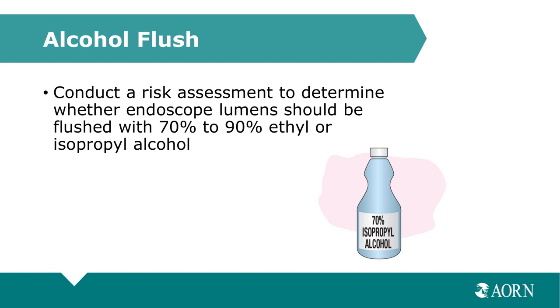Many clinical practice guidelines and many experts in the field recommend manual or mechanical flushing of the endoscope lumens with alcohol because it helps to facilitate drying of the endoscope lumens by binding with residual water, and this enhances evaporation. However, flushing of the endoscope lumens with alcohol just might not be necessary if your endoscope has been effectively cleaned and thoroughly dried. And because of the fixative properties of alcohol, this practice is not recommended in many countries.